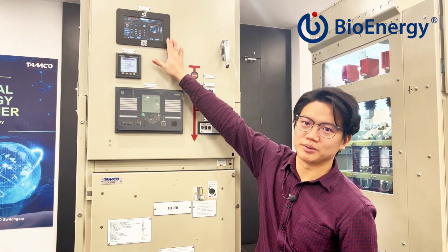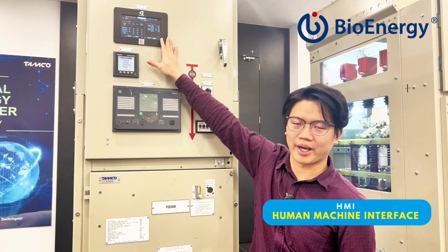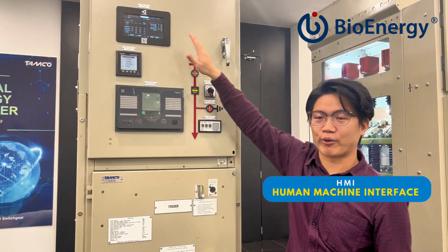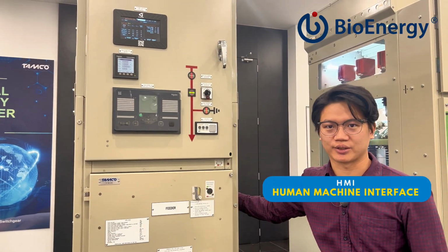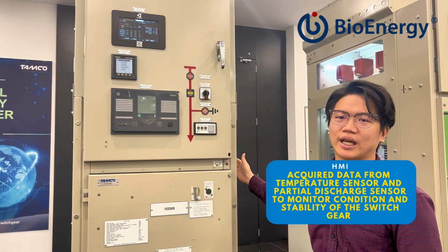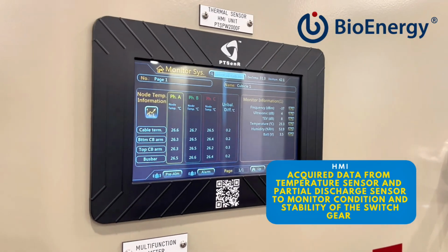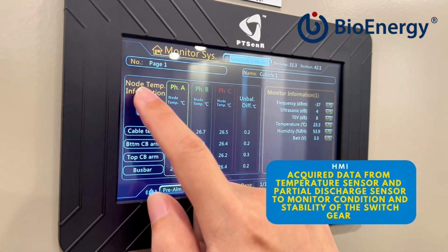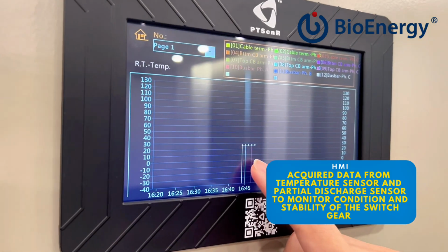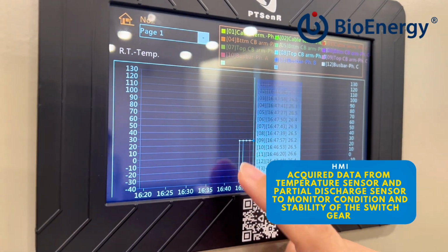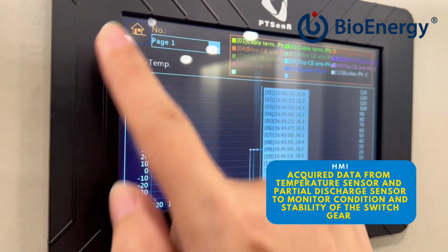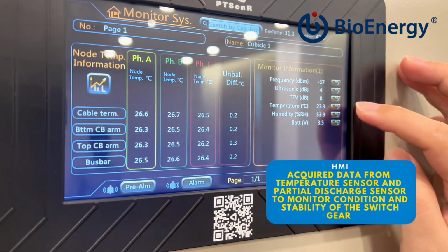This is a human-machine interface, an HMI. So this HMI actually acquires data from the temperature sensors. The temperature sensors and the partial discharge sensors will send the signal to this HMI, and then this HMI will acquire the data to monitor the health, the condition, and also the stability of the switchgear.